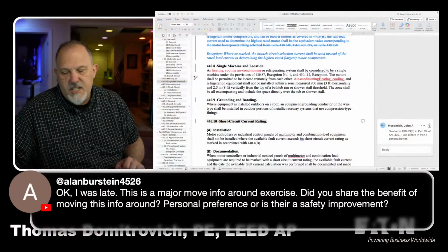Now I could translate that into the safety issue that was in 422, which I have to deal with too. 422 says that for central heating equipment, I think it's heating, you need to have a receptacle or something like that. A few inspectors have told me they got into debates with contractors because the contractor said, well, I don't need to pull a receptacle there. And then the inspector would say, yeah, it says in here in 422. And they would say, well, that says central heating equipment. This is not central heating. It's central heating and cooling equipment. It's listed as both. And they would go round and round and round. And you know who wins that one. But it causes confusion. And then there's a bunch of other examples. So that's why we're doing this. Hopefully that helps explain it for you.